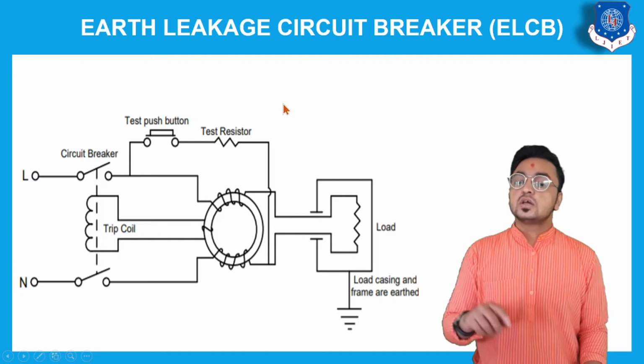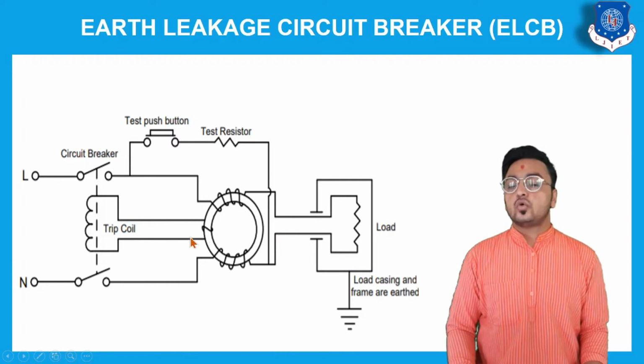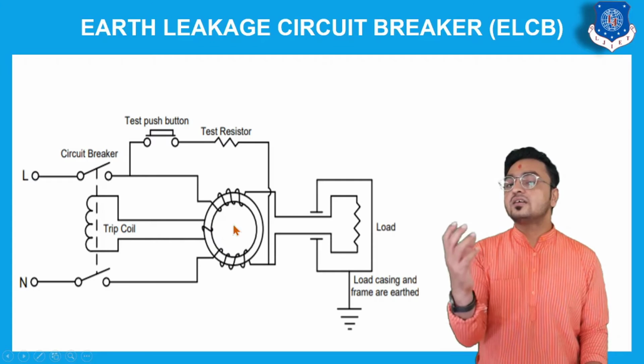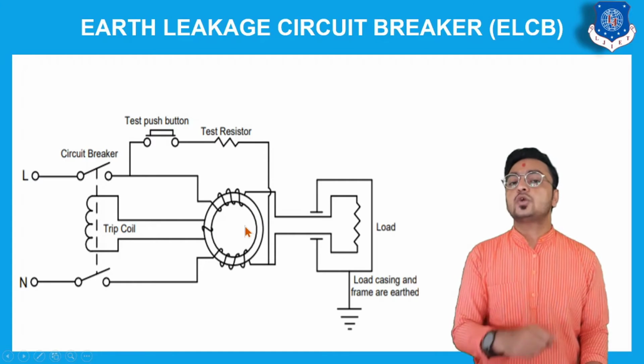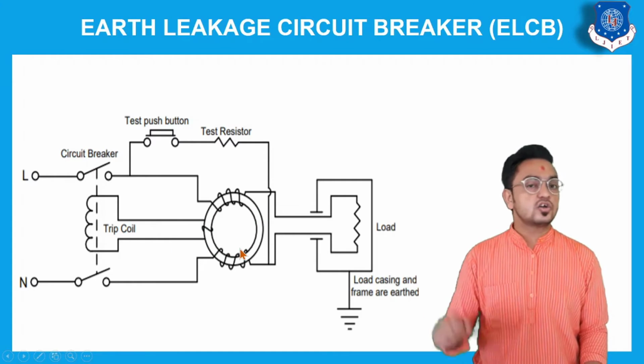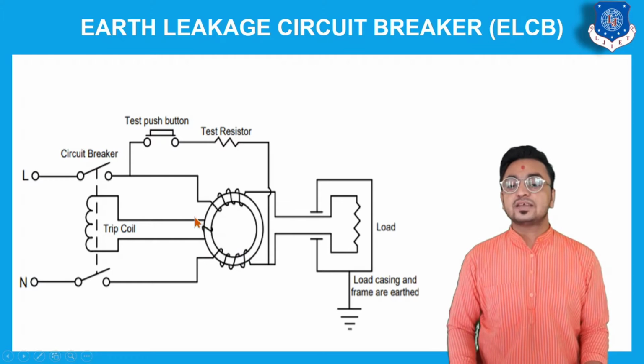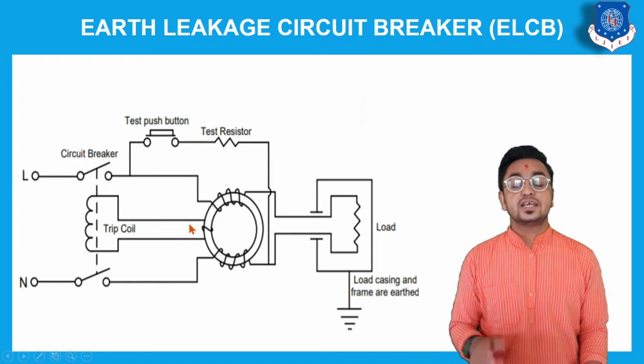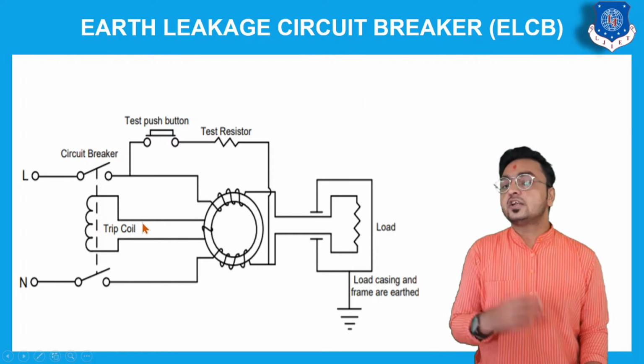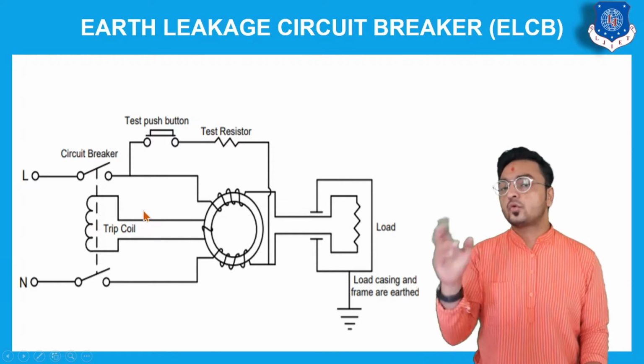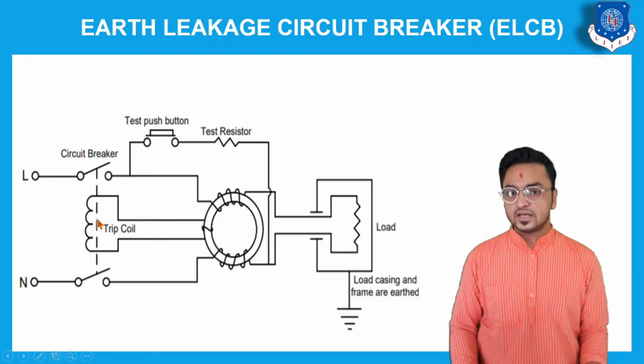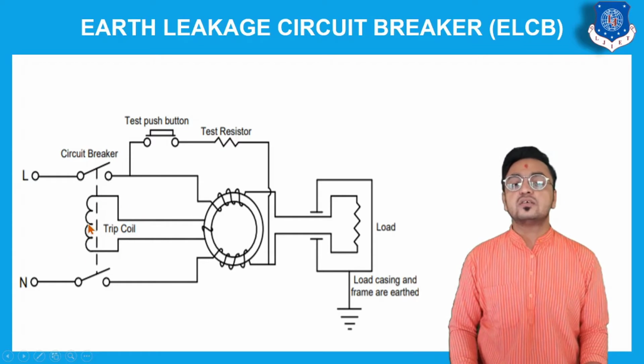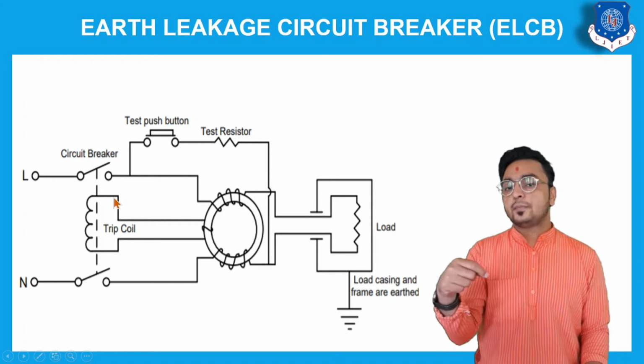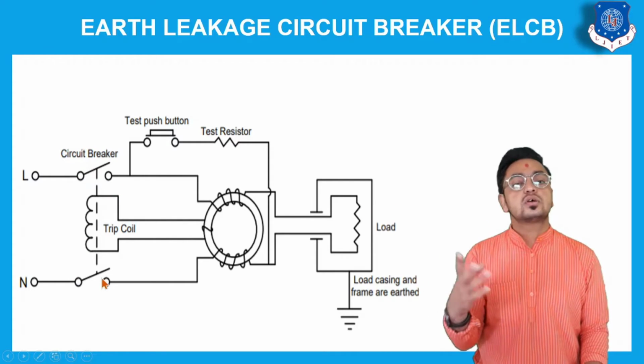We had arranged a third coil. When resultant flux is generated, it generates EMF in this third coil, and this EMF is provided to a trip coil. When this trip coil gets current, it produces its own magnetic flux, and this flux operates a switch in between the two conductors.